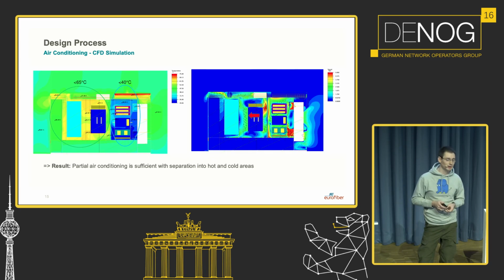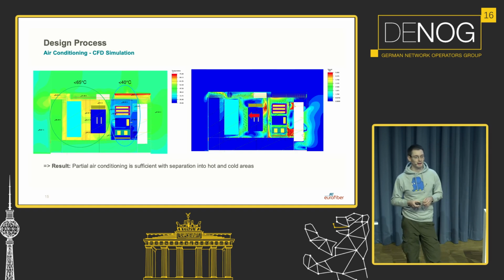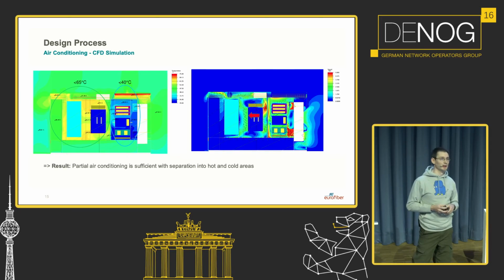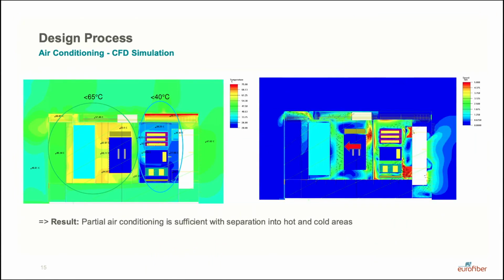On the right-hand side, we also got an airflow velocity simulation from the engineering company that ran it for us. The arrows represent the airflow direction in the cabinet, and the colors represent the airflow velocity. That was really useful to make sure the air exhaust of one device wouldn't end up directly at the air intake of another device, which would be bad. We could also optimize the airflow a bit by putting a metal sheet here and there to redirect air.